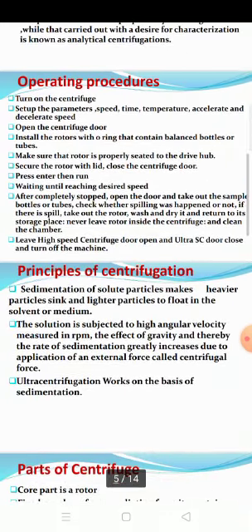Now the operating procedure of ultracentrifugation. First of all, turn on the centrifuge and set up the parameters: speed, time, temperature, accelerate and decelerate speed. Open the centrifuge door and install the rotor with O-ring that contains balanced bottles or tubes. Make sure that the rotor is properly seated on the drive hub. Secure the rotor with its lid and close the centrifuge door. Now press enter, then run, waiting until the desired speed is reached. After it has completely stopped, open the door and take out the sample bottles or tubes.